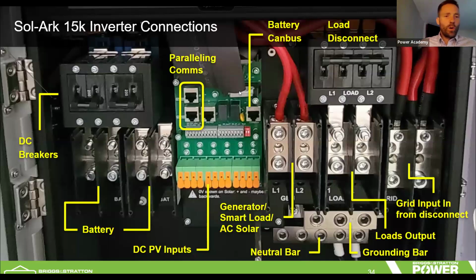Okay, sorry. So on the DC side, we've got dual battery inputs on the Sol-Ark 15K. So you've got the 2 positives here, and these breakers are both on the single positive pole for the battery inputs. Then you've got the dual negative inputs on the batteries. So for 1 or 2 stacks of 6.6 batteries, you're good to go without a combiner. If you're paralleling units, you would use these communications ports here. The battery CAN bus will come out of a single one of the batteries in the bank. So it doesn't matter which battery, but you'll use one of the batteries to connect through the battery CAN bus here. All of the batteries would be daisy chained with the communications. I'll show an example of that in a minute.